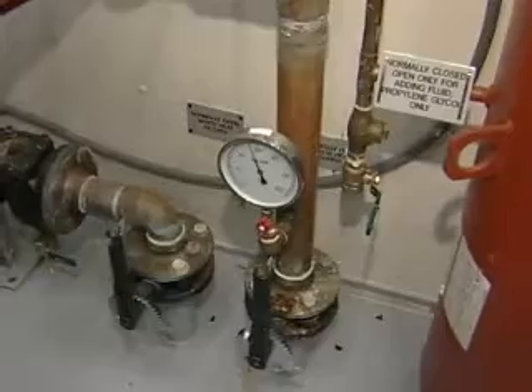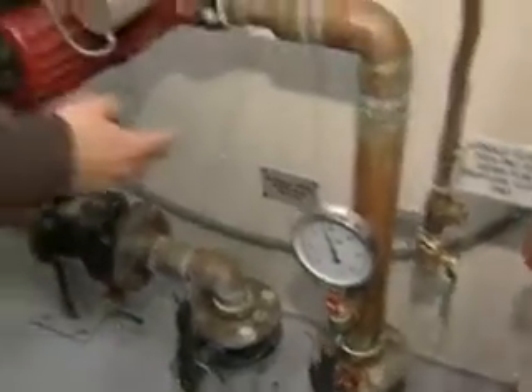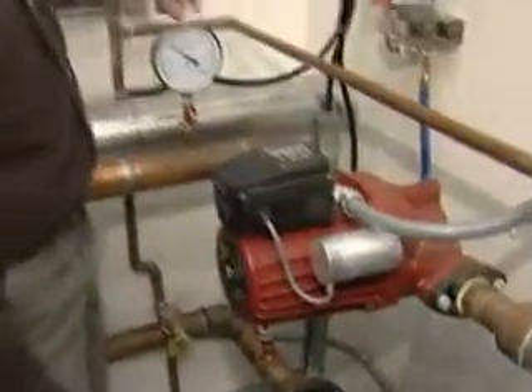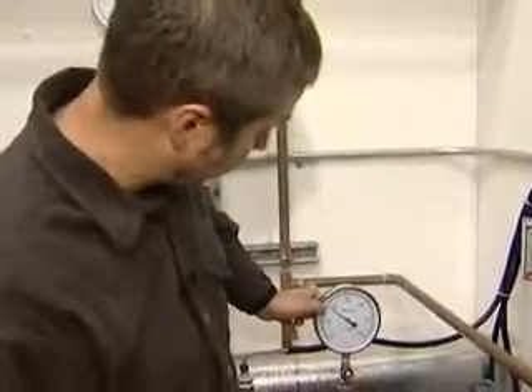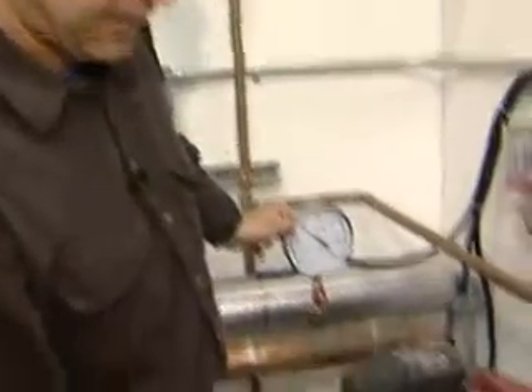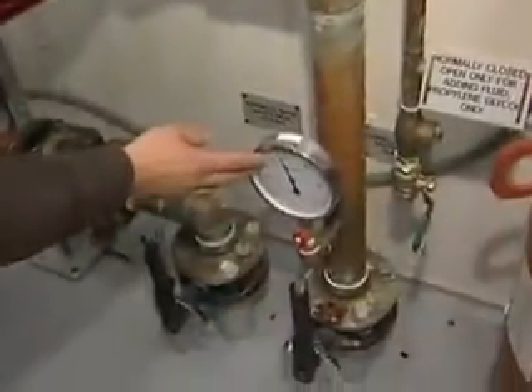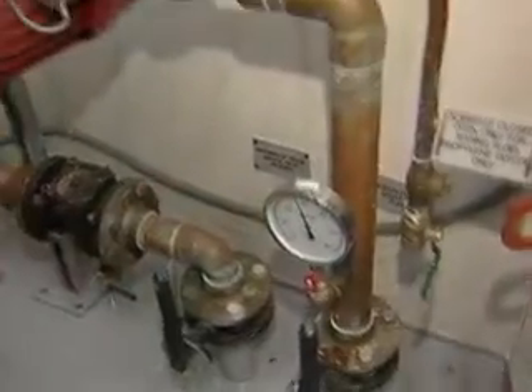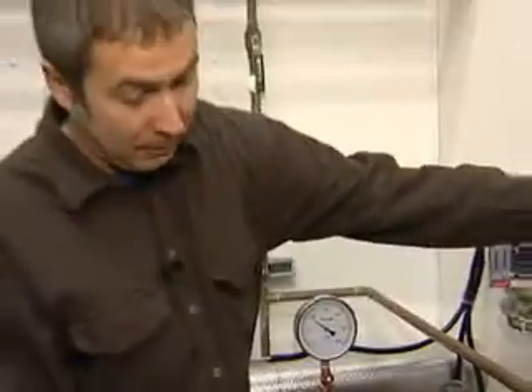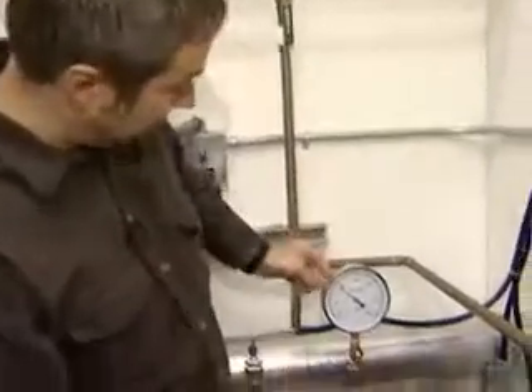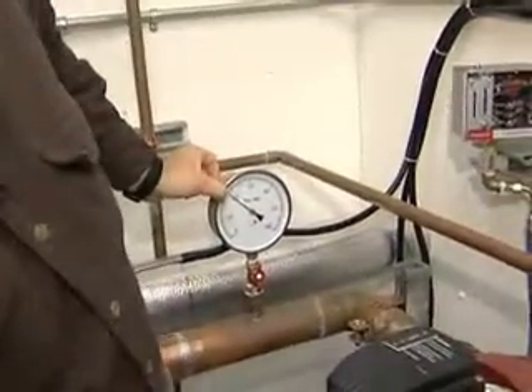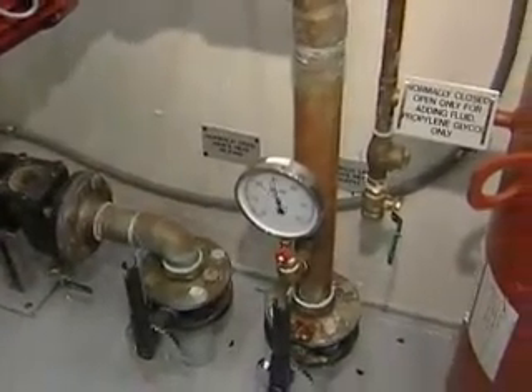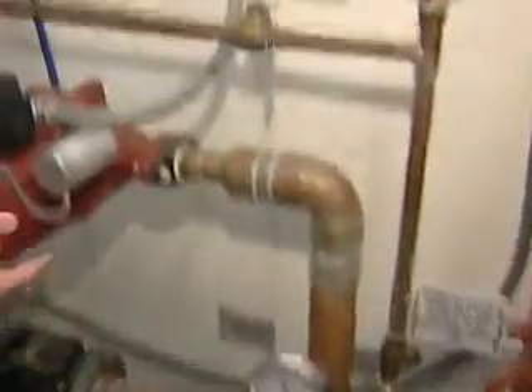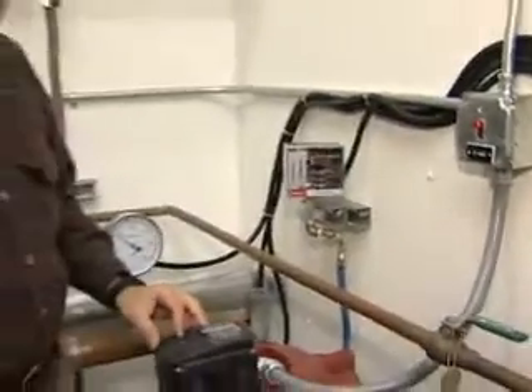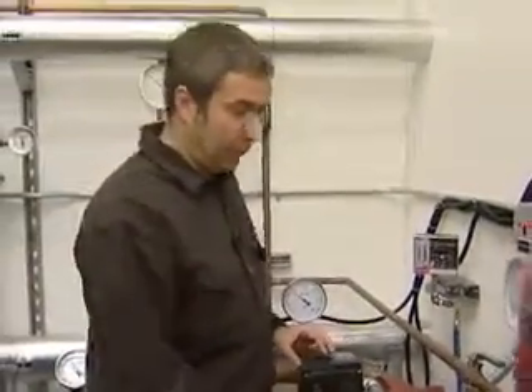So typically the pressure, if the pump is working, will always be higher on the downstream end than it is on the upstream end. So here we have a pressure of about 18 psi coming into the pump and a pressure of about 27, 28 psi going out. Now if I turn the pump off, we'll see these pressures equalize. So now we have approximately 19 psi upstream and downstream. When I turn the pump back on, the pressures go back. So you can verify that each pump is operating through that.